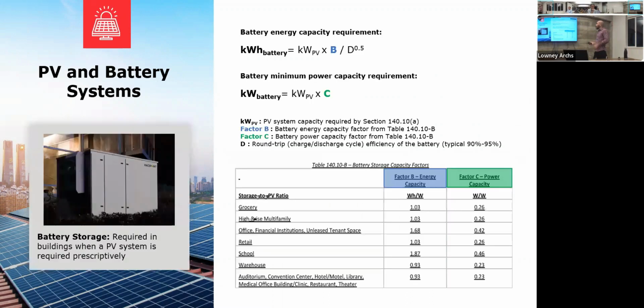And then after you calculate the PV capacity, we look at the second table for battery capacity calculations. This is solely based on the building type. So based on your building type, you pick a factor for your building and then you multiply the PV capacity previously calculated with this factor, and then you come up with your battery size, and it'll make more sense when we do an example.